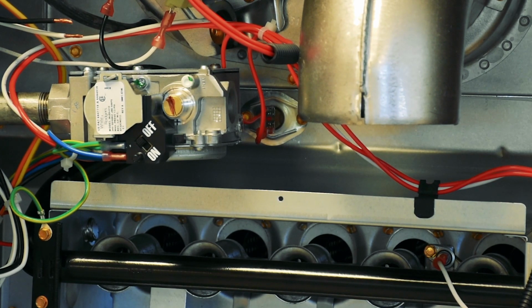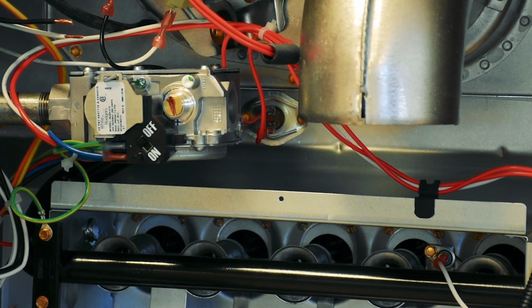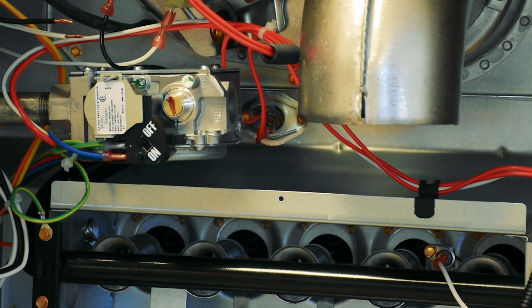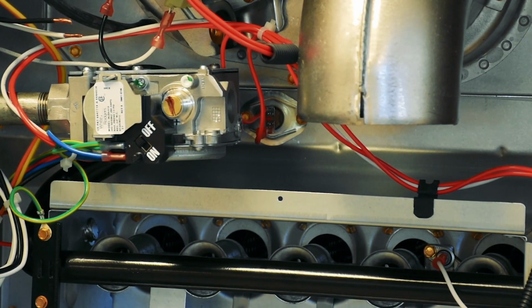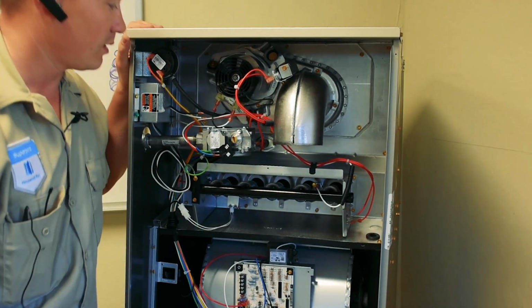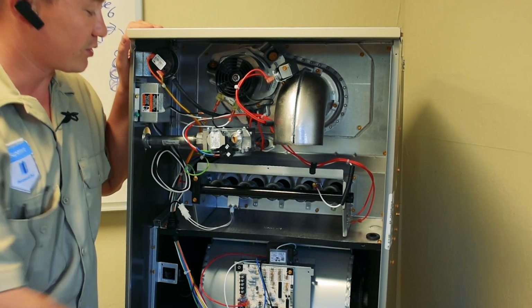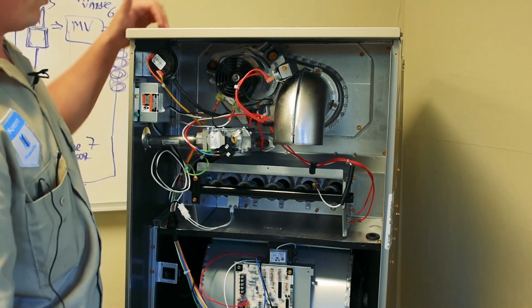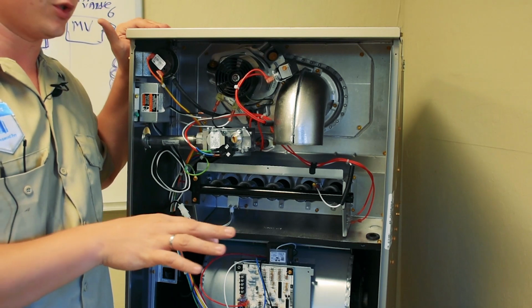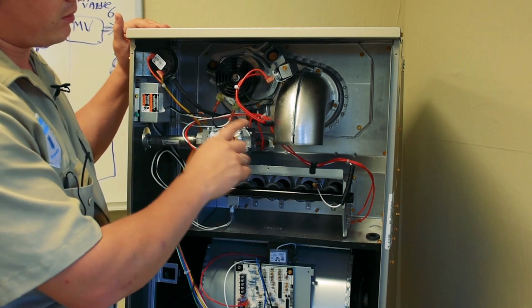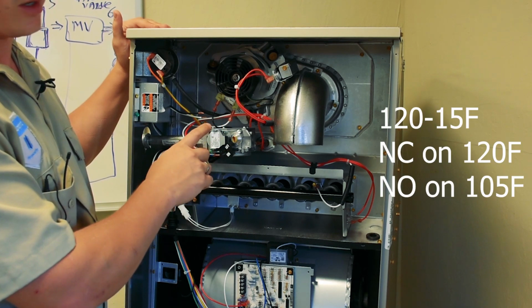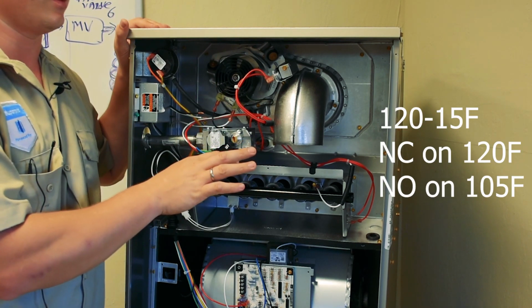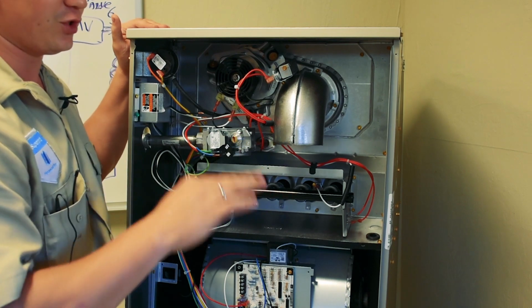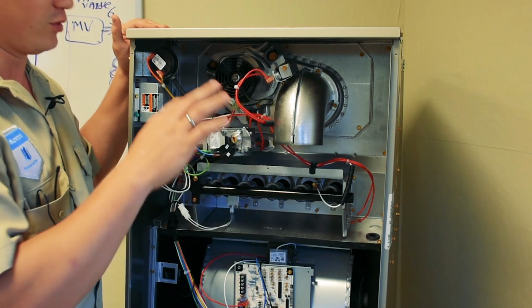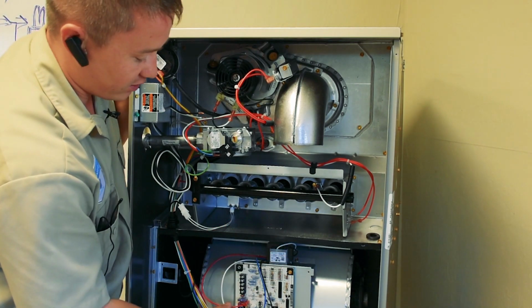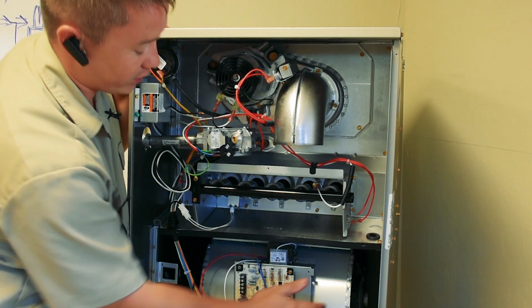After that, the air handler, the blower wheel motor, is still running and removing the heat from the heat exchanger, because the heat exchanger is still hot. It will run the blower wheel motor because the high limit switch is still hot. Usually that high limit switch has a sign of 120 minus 15 Fahrenheit, which means that when the high limit switch reaches 105 Fahrenheit, it will turn off the relay on the control board, which is running the blower wheel motor. That's it.